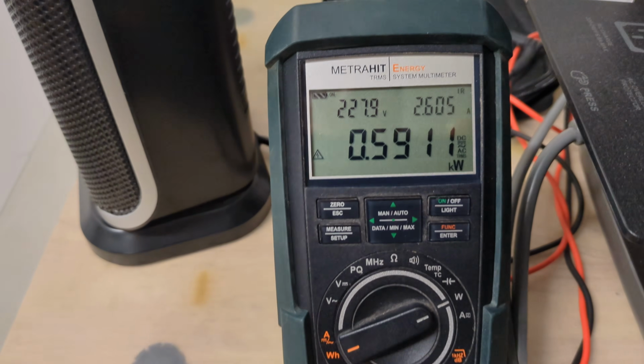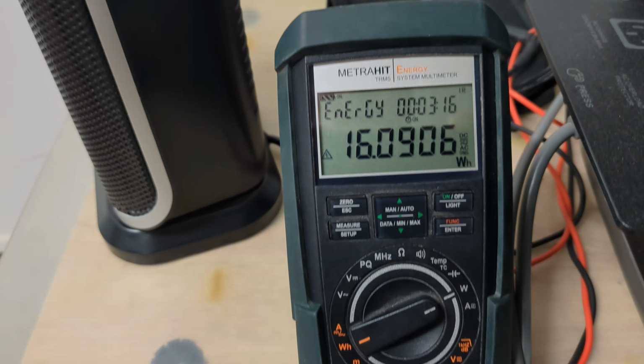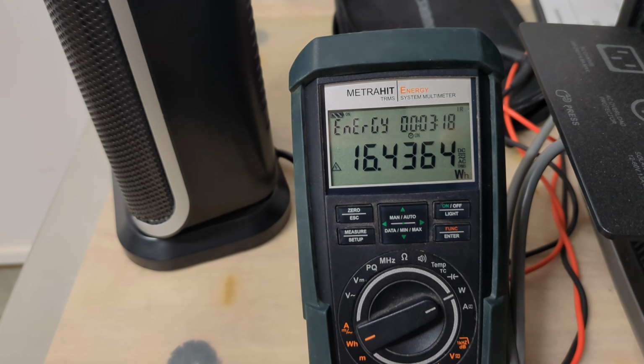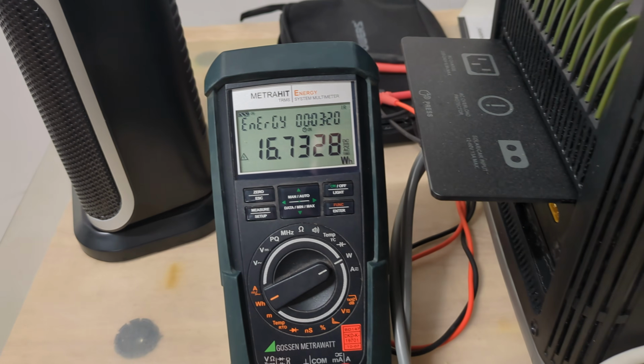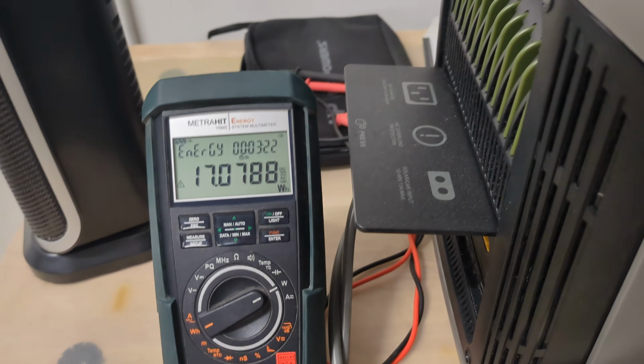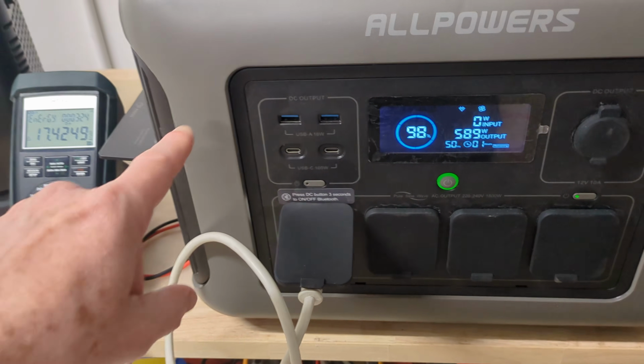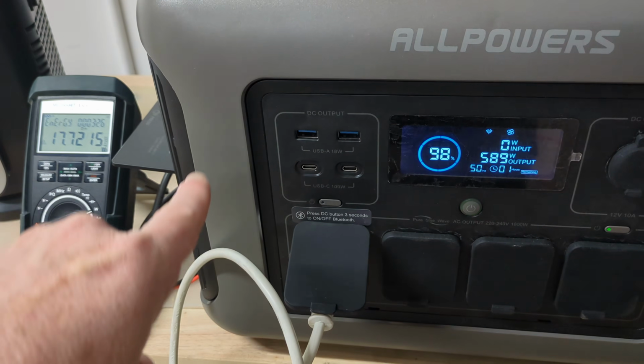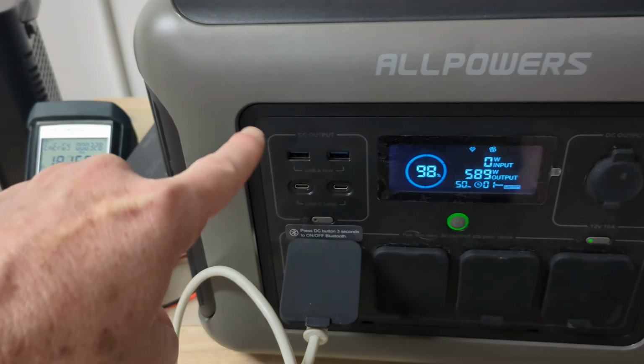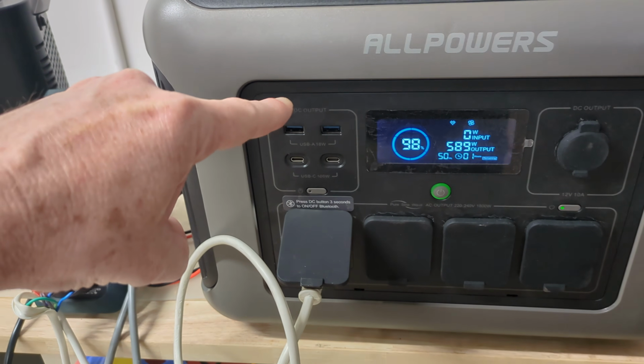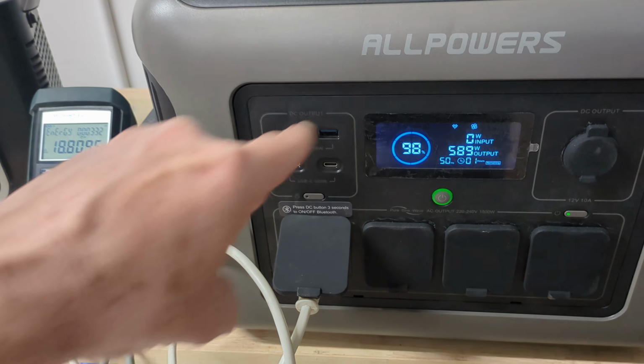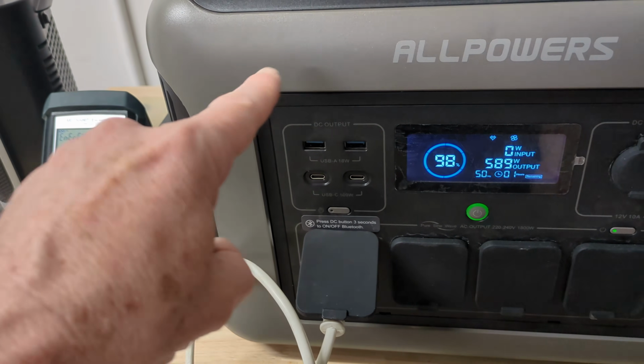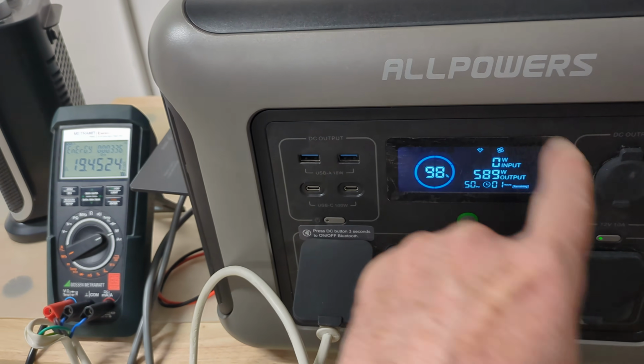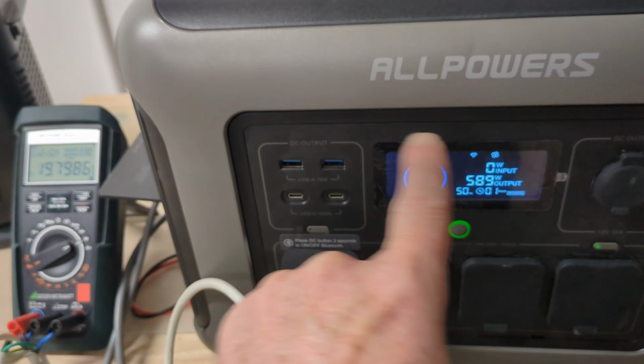We're measuring 590 on here, and we've been monitoring the energy for 3 minutes. It should be, I think, closer to the capacity, because you'll be looking at a different part of the efficiency curve. There's a peak in the efficiency curve based on load power, dropping off at low loads and also at higher loads, but with a fairly big sweet spot in between.